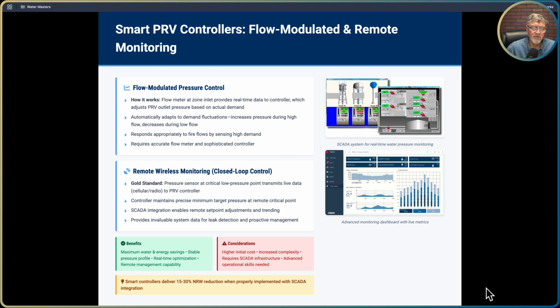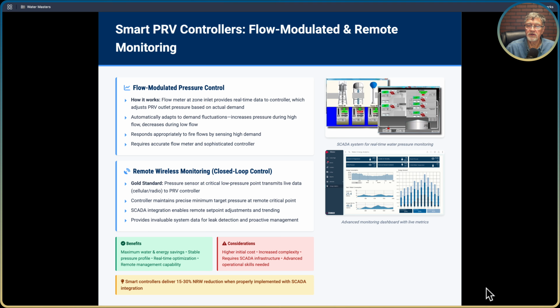So, lastly, we have our remote wireless monitoring closed loop control, and this is kind of the gold standard of sophisticated pressure modulation, and if you want to really do it right, this is the way to do it because it's a pressure sensor at a critical low pressure point. It transmits live data via cellular or radio, and some even have LoRa types of communications to the PRV controller. The controller maintains precise minimum target pressure at the remote critical point.